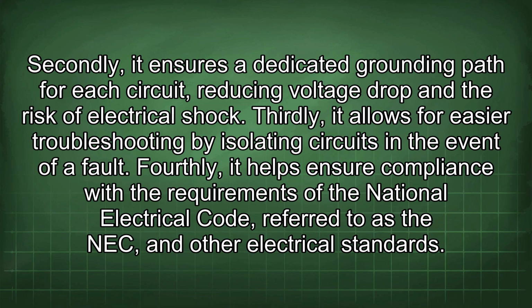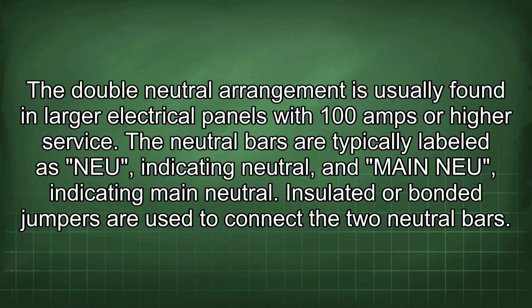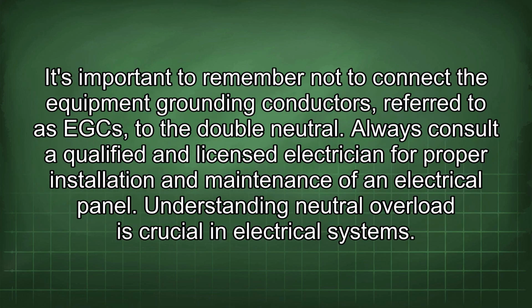electrical standards. The double neutral arrangement is usually found in larger electrical panels with 100 amps or higher service. The neutral bars are typically labeled as NEU, indicating neutral, and MAIN-NEU, indicating main neutral. Insulated or bonded jumpers are used to connect the two neutral bars. It's important to remember not to connect the equipment grounding conductors, referred to as EGC, to the double neutral. Always consult a qualified and licensed electrician for proper installation and maintenance of an electrical panel.